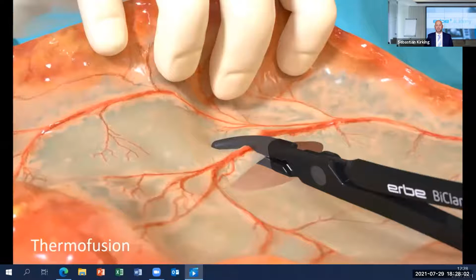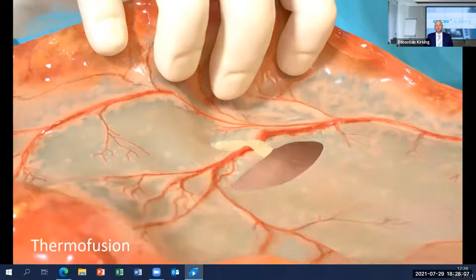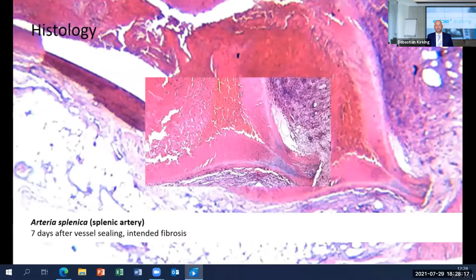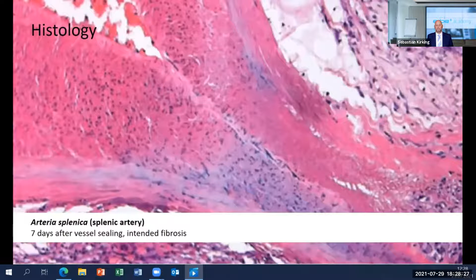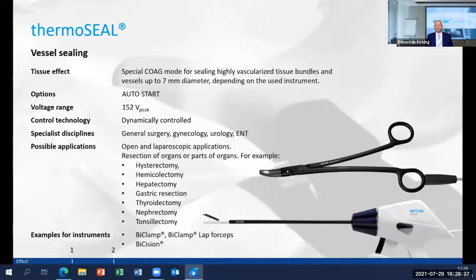Another type of advanced electrosurgical technology are thermofusion and vessel sealing modes and instruments. While regular coagulation modes are rather used for capillary bleeding and on smaller vessels, thermofusion and vessel sealing modes are designed to seal larger vessels. The vessel walls are compressed by the jaws of the instrument. The compression is very important for the effectiveness of the seal. With the start of activation, the generator will measure the electrical characteristics of the tissue and perform a technically controlled coagulation that results in a thermal seal of the vessel. This is not only about the generator's control technology, also the instruments have to be specially designed for vessel sealing.